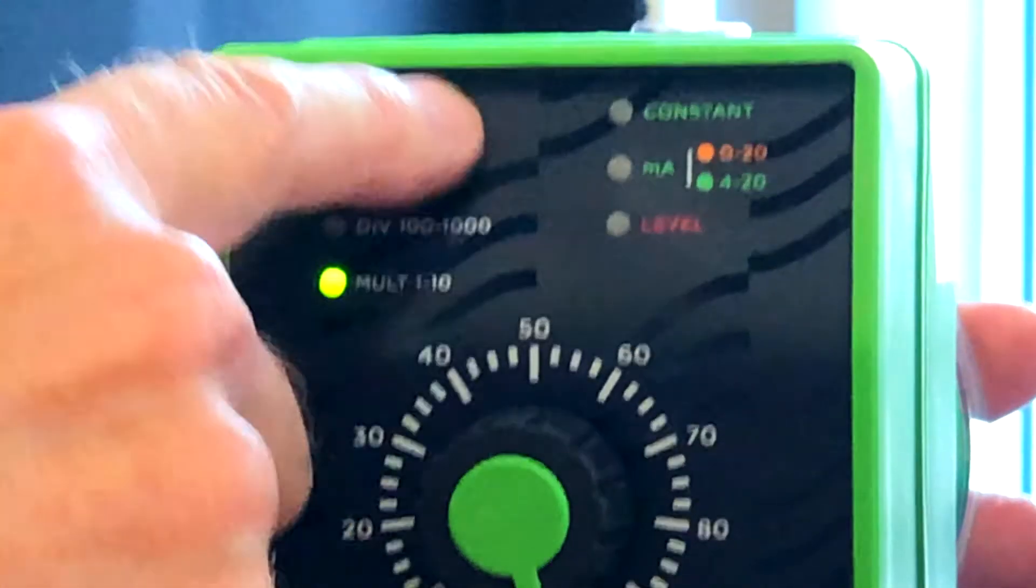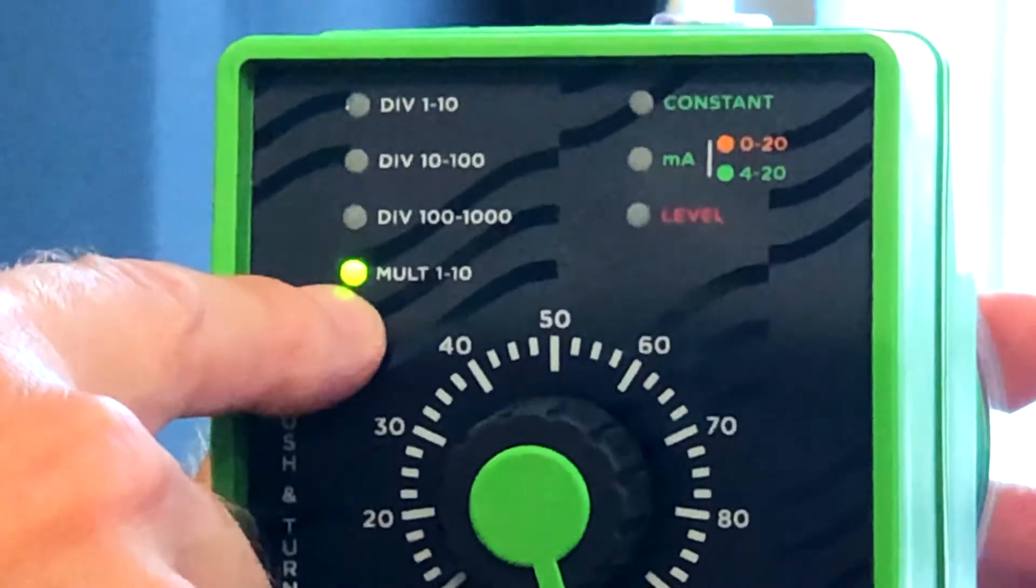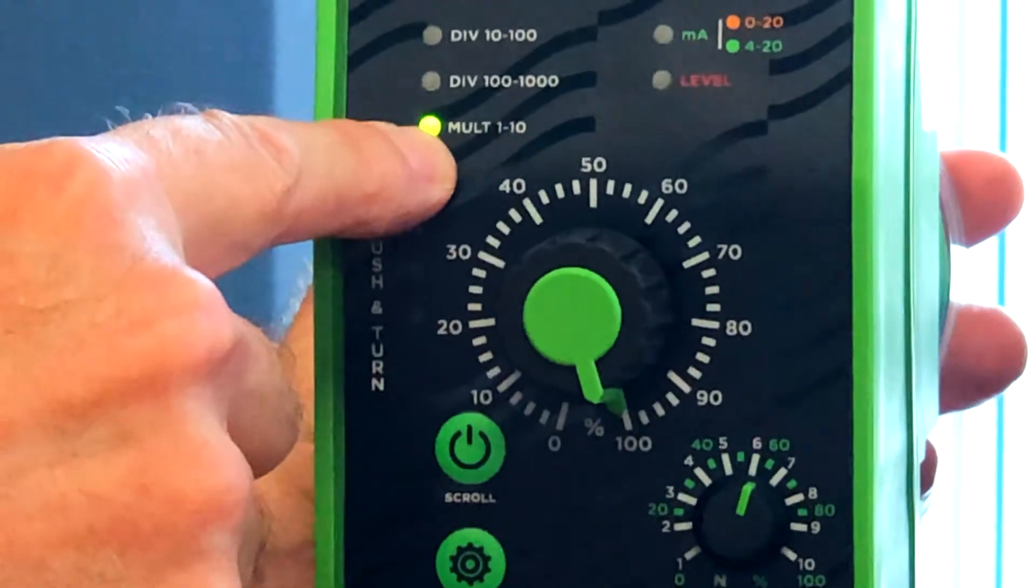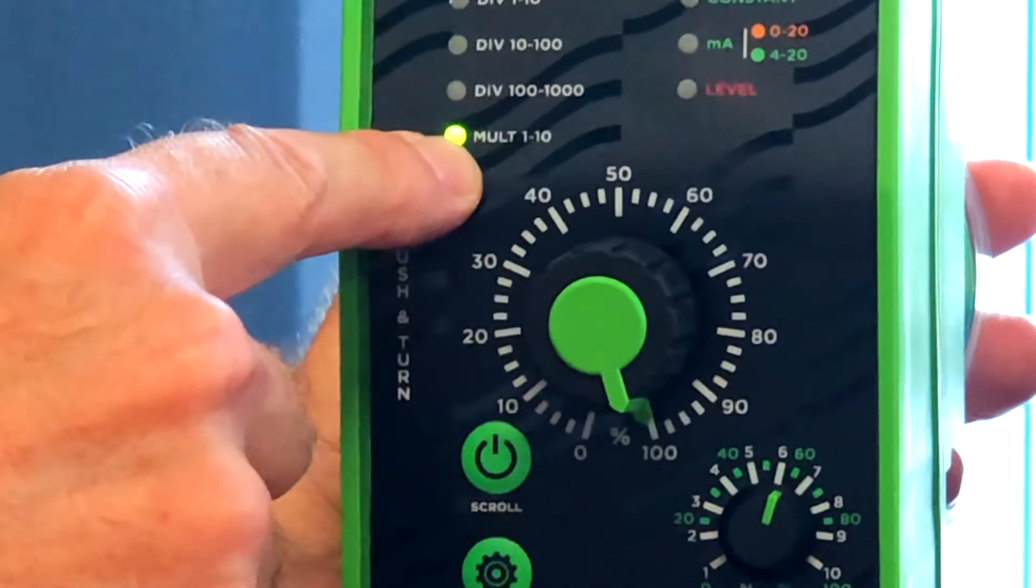So when you're actually in one of the white modes, such as the one we're in now, which is multiply 1 to 10, the actual dial serves as a factor rather than a percentage. So if I turn the dial to position 6 in white, it means that it's multiplying by 6, which means that one pulse in will give you 6 strokes out.